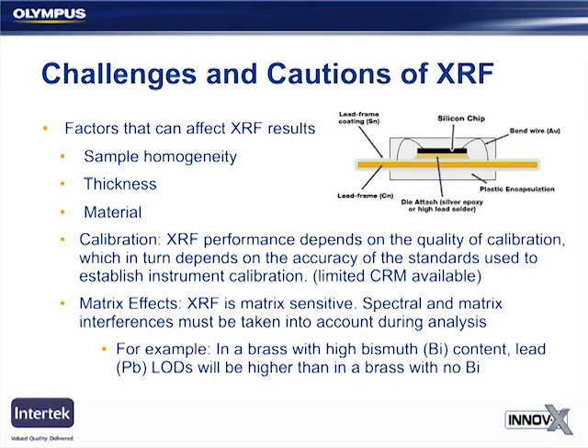Just as an example, if you're testing for lead in brass alloys, some grades of brass alloys contain high bismuth content. Because of some line overlaps, an alloy with high bismuth content will have a higher lead detection limit than an alloy with no bismuth content. And so if you see detection limits changing like that, that's one thing to look for: matrix effects, what kind of interferences are present.